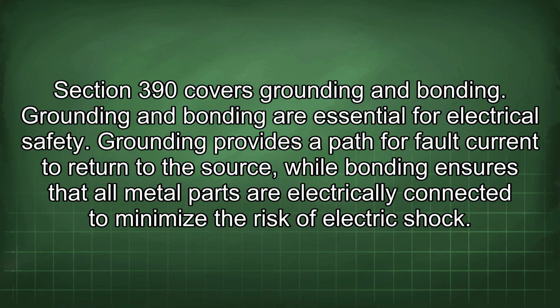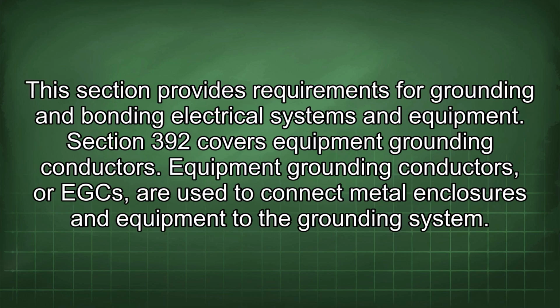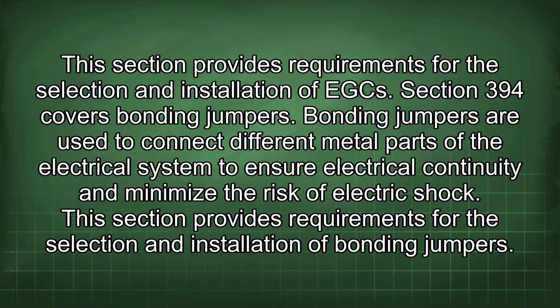Grounding provides a path for fault current to return to the source, while bonding ensures that all metal parts are electrically connected to minimize the risk of electric shock. This section provides requirements for grounding and bonding electrical systems and equipment. Section 392 covers equipment grounding conductors. Equipment grounding conductors, or EGCs, are used to connect metal enclosures and equipment to the grounding system. This section provides requirements for the selection and installation of EGC.